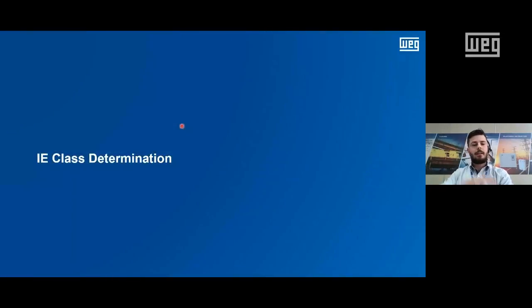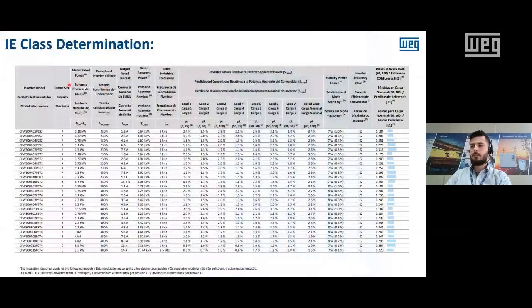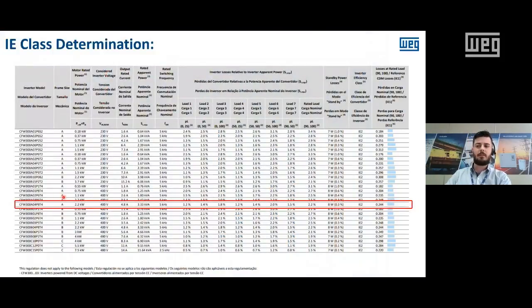Okay, so these are the technical basics, and you're probably thinking how you can confirm these values, or how you can calculate the IES class for a power drive system. I'm going to make some examples here for you so you know how to do this by yourself. So if you go to that exact same file, let's have an example here, a CFW300, 4.8 amperes, 400 volts, which is this one here. It's rated for operation with a 2.2 kilowatt motor.